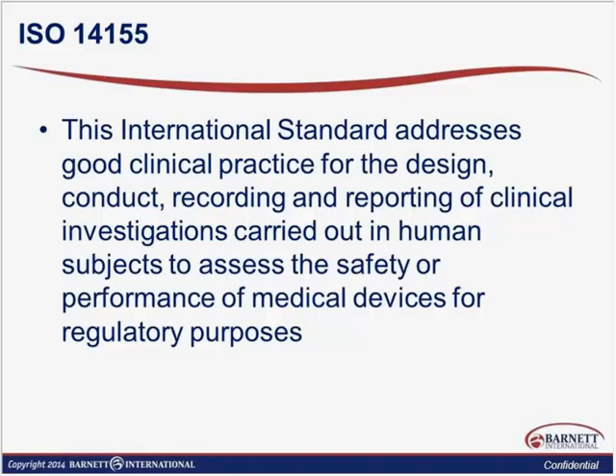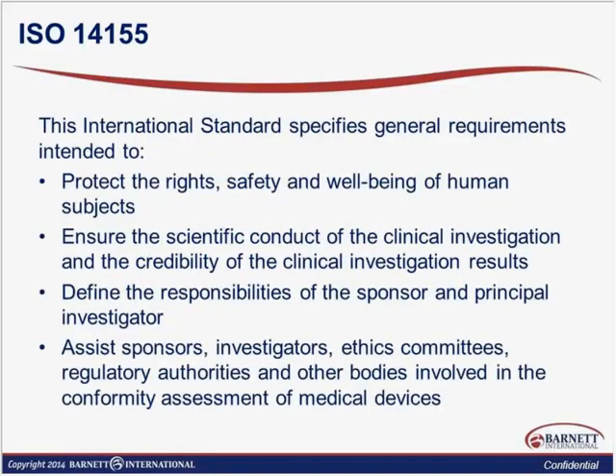ISO 14155 addresses GCP for designing, conducting, recording, and reporting clinical investigations carried out in human subjects where we are assessing safety or performance of medical devices for regulatory purposes. It talks about protection of rights, safety, and welfare of human subjects, making sure that we are conducting that protocol according to the plans that we have set forth, so that we have a scientific approach to the conduct of that study and that we can rely on the credibility of the data generated. It also speaks to the responsibilities of sponsors and principal investigators, and we'll see it's a little bit different from ICH E6, which also talks about the role of ethics committees or institutional review boards. It is used as a tool for sponsors, investigators, ethics committees, regulatory authorities, as well as other bodies to determine whether these studies are being conducted in a uniform manner, applying these standards to ensure uniformity in our processes.